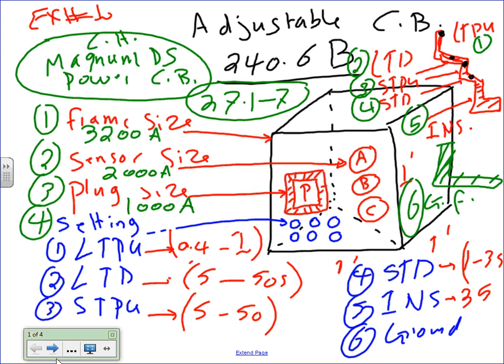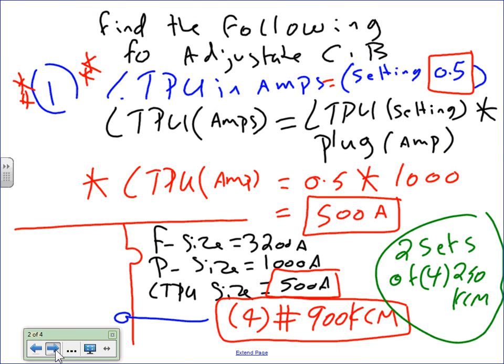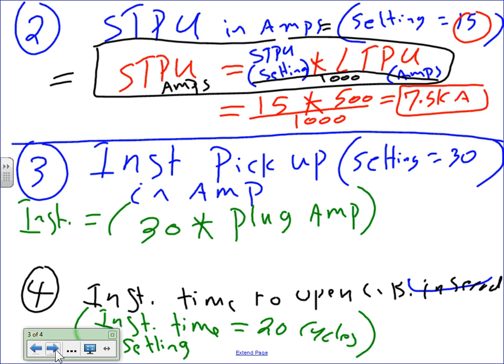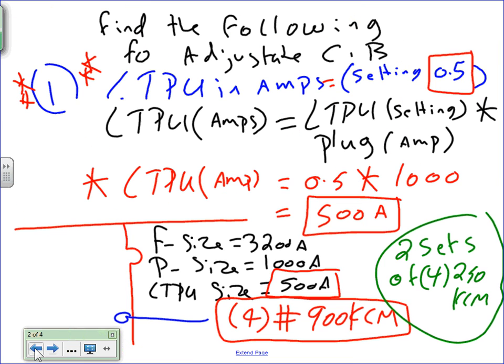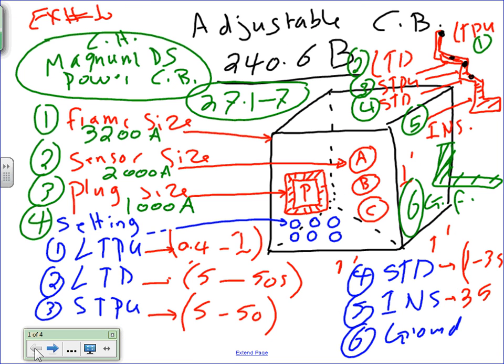Cool? Okay. Before we do that, we're going to do the instantaneous. Let me go to the instantaneous. The instantaneous, Chris, is right this little piece here. I want to size this piece. So here's 1, here's 2. These are my 3 pickups. Can you guys see these 3 points are 3 pickups? I'm going to go size the third one, which is the instantaneous piece, that leg.